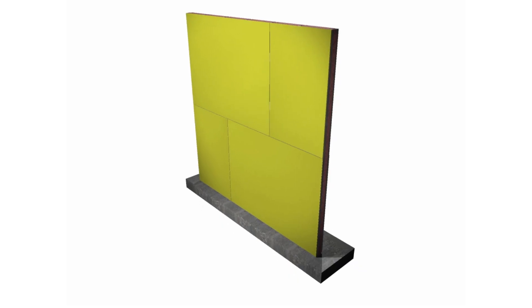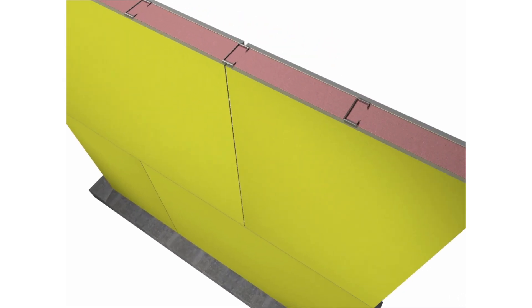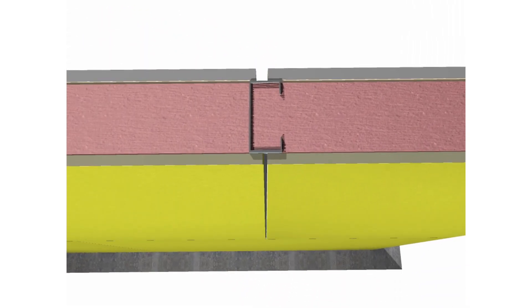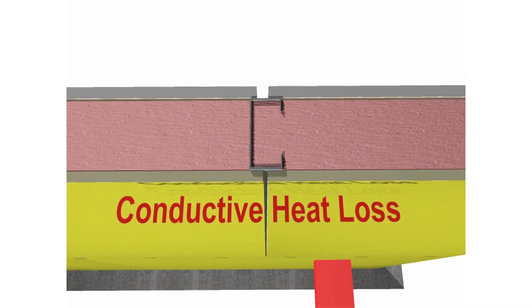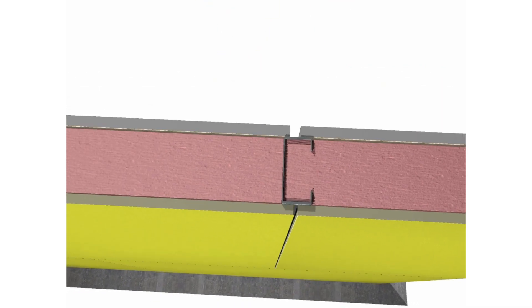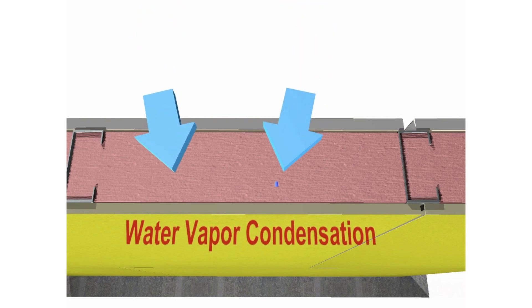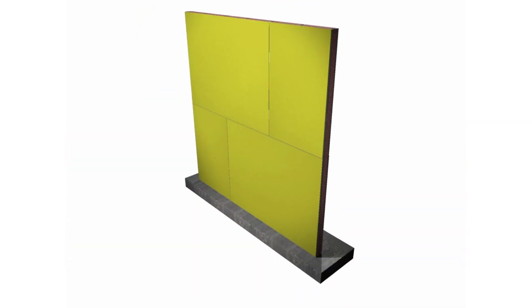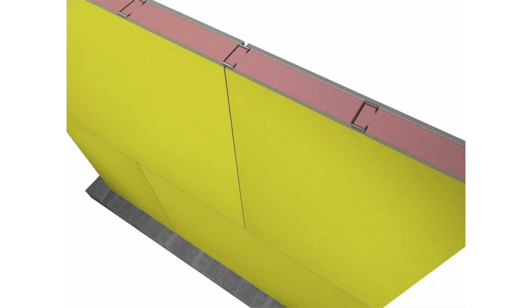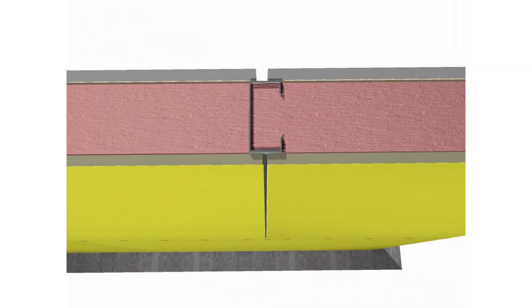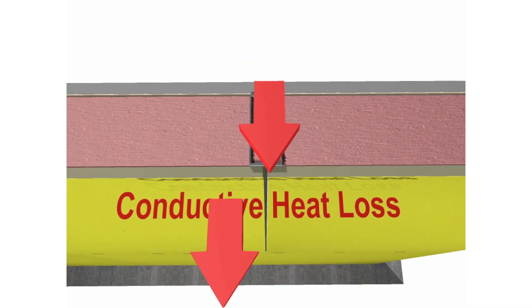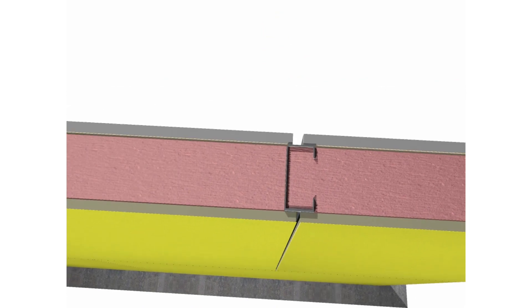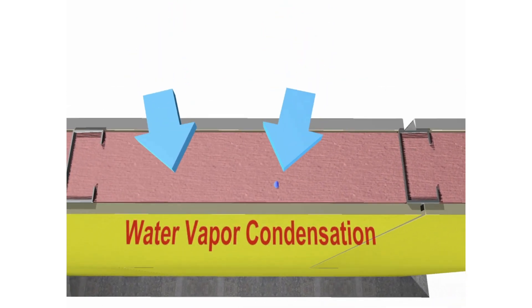As shown here, when insulation is only placed between the studs, the steel serves as a thermal short circuit, allowing heat to move around the cavity insulation very quickly. This ultimately causes a thermal bridge and is a major concern because it can drastically reduce the thermal performance of the insulation placed between studs, which can contribute to building energy loss and potential condensation issues.